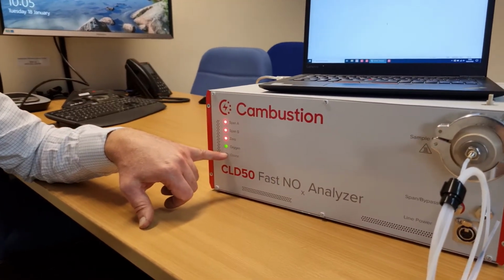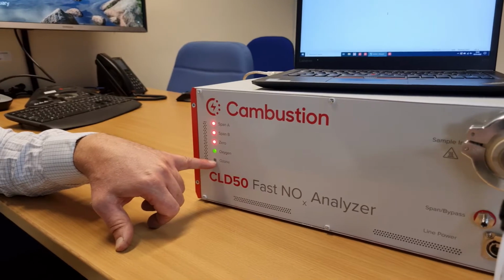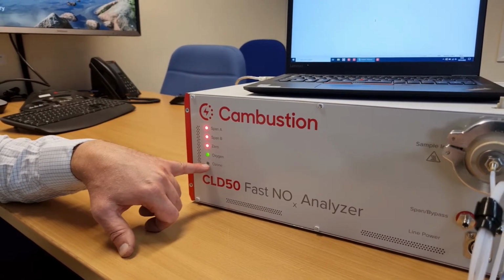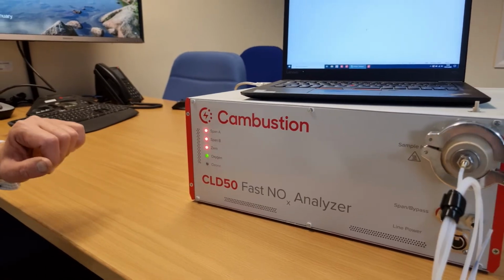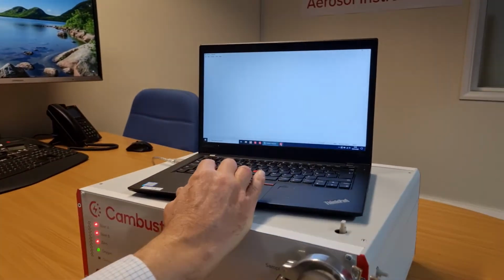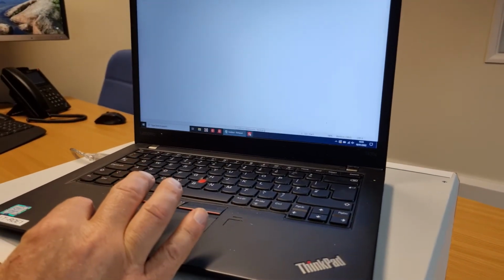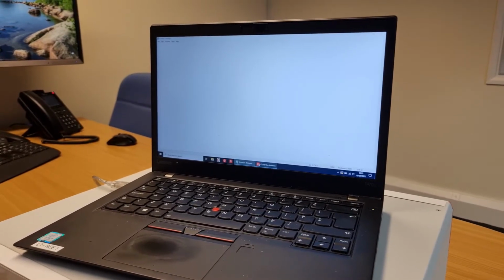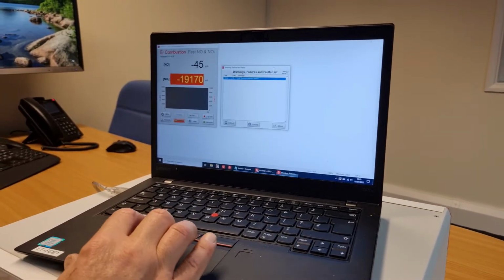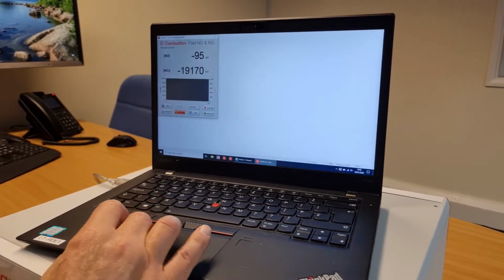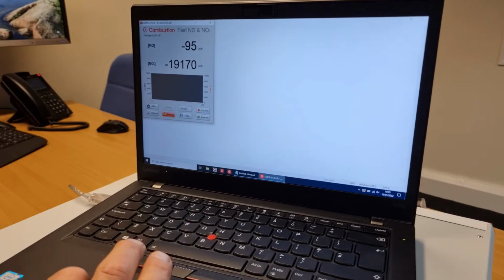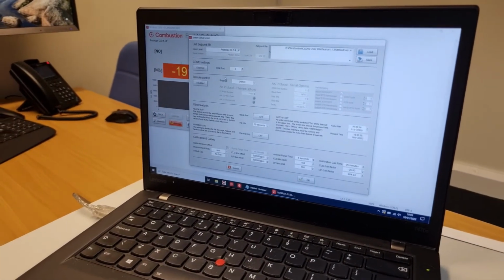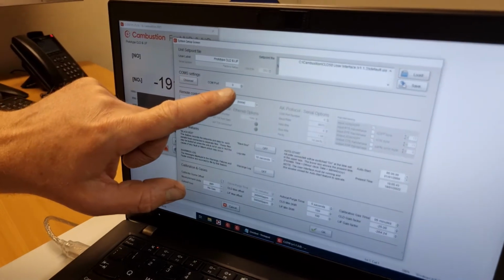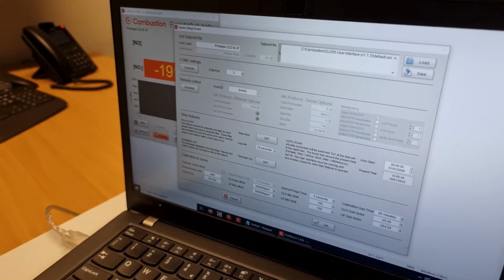Once the instrument starts to warm up and ozone is produced for the chemiluminescence detector, then the ozone light will illuminate also. The user interface, you'll find on the desktop with this kind of icon for the CLD50. If I start the user interface, we need to first of all establish the correct communications port. If I take the advanced setting, in here there is comms setting, COM port here is set to number 3, and that matches the COM port which we'll find under settings.